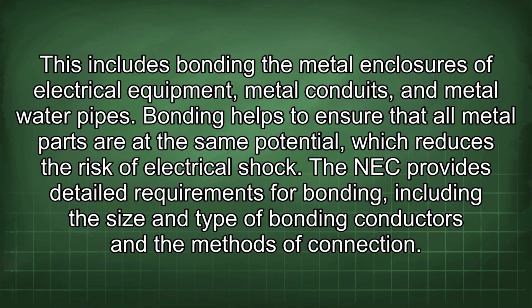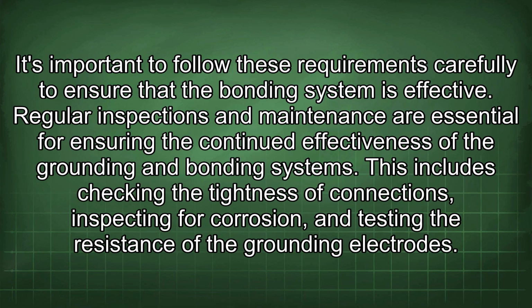The NEC provides detailed requirements for bonding, including the size and type of bonding conductors and the methods of connection. It's important to follow these requirements carefully to ensure that the bonding system is effective. Regular inspections and maintenance are essential for ensuring the continued effectiveness of the grounding and bonding systems. This includes checking the tightness of connections, inspecting for corrosion, and testing the resistance of the grounding electrodes.